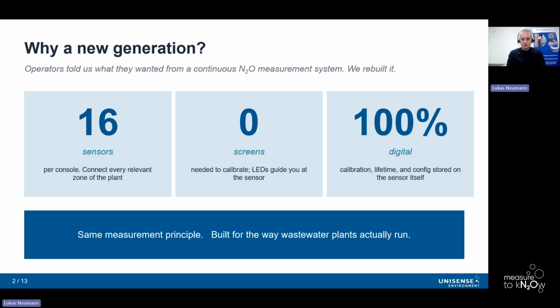Next, you need exactly 0 screens to calibrate these sensors. So the new sensor, in combination with the connector unit, walks you right through the 2-point calibration procedure with some LEDs. We have a video showing this in just a minute. And then we have the new digital sensor body, which logs all calibration data, lifetime tracking, and the sensor configuration, all live on the sensor itself rather than on the console as before. So the takeaway here is that it's the same proven measurement principle, the validated Clark type electrochemical sensor. What we've changed is how you work with it.